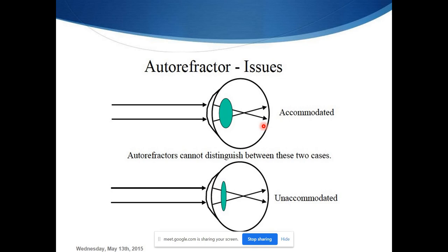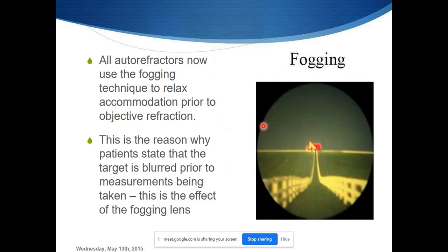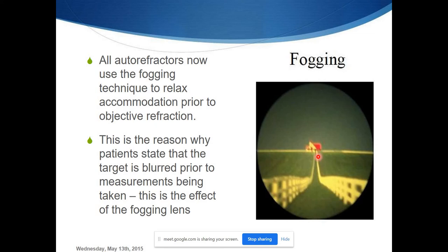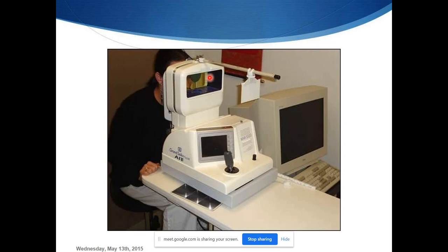A major issue with autorefractometers is that they cannot identify whether the eye is accommodating or not. To overcome this, a fogging or blurring of the image is induced — this is the fogging technique. Once the image is fogged, accommodation relaxes, and only after that does the instrument measure the refractive error. This is why patients often report blurring just before the measurement.